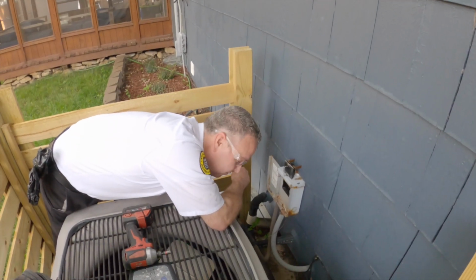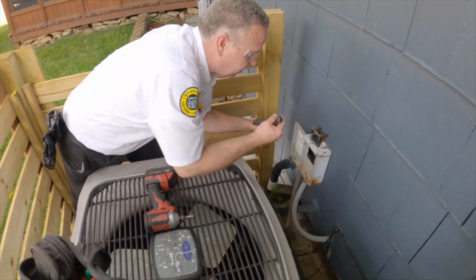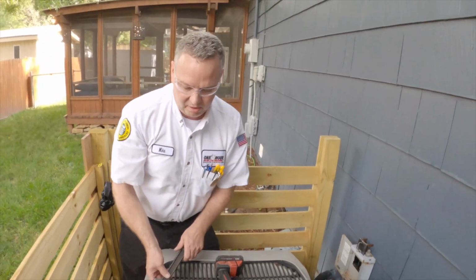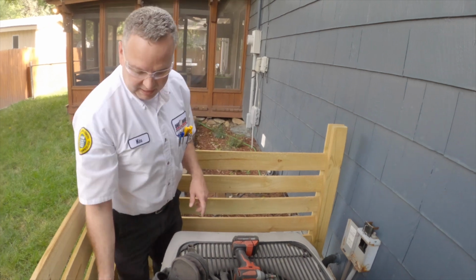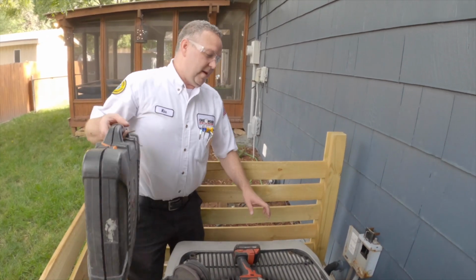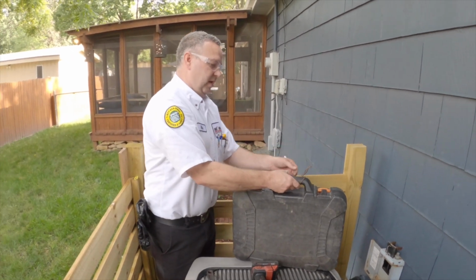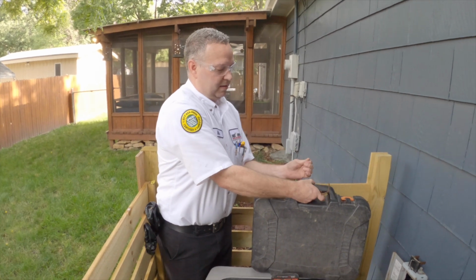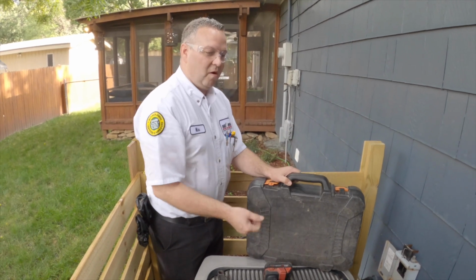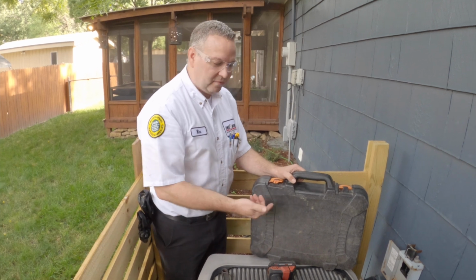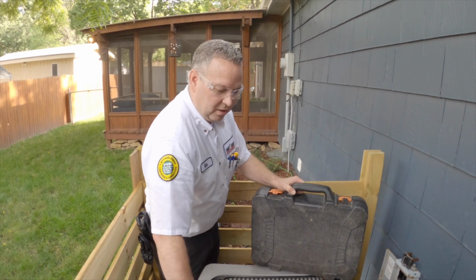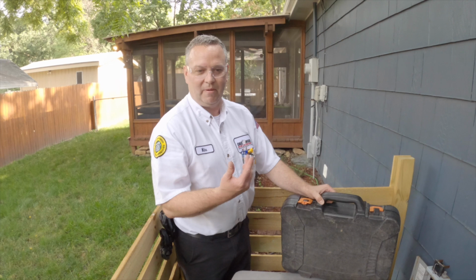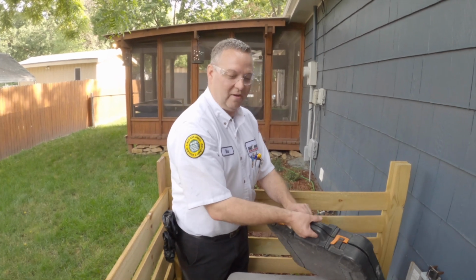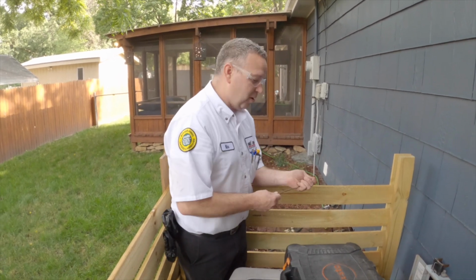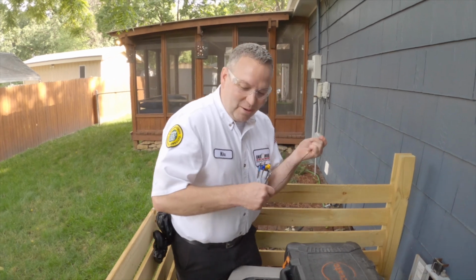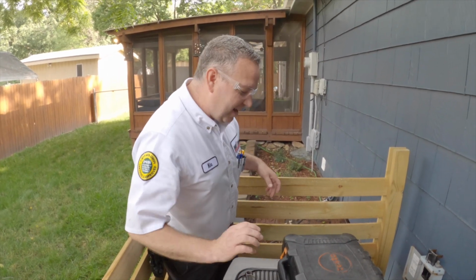Believe it or not, when I first started in this industry, I ran into the same style unit. This unit's a little unique — it has what's called king valves. Basically, you put your refrigerant gauges on this style of system, and then you have to open up a valve. I didn't realize it doesn't have Schrader valves, and come to find out, all I had to do was open that valve — it wasn't actually low on refrigerant.